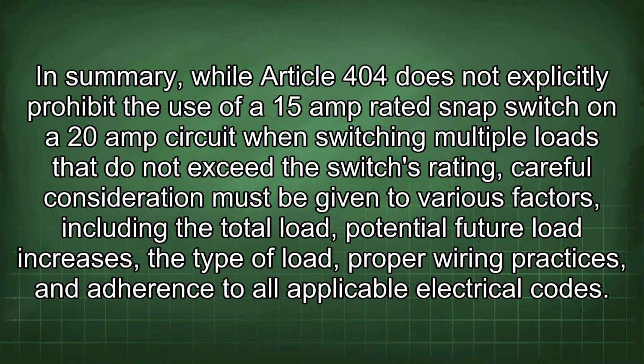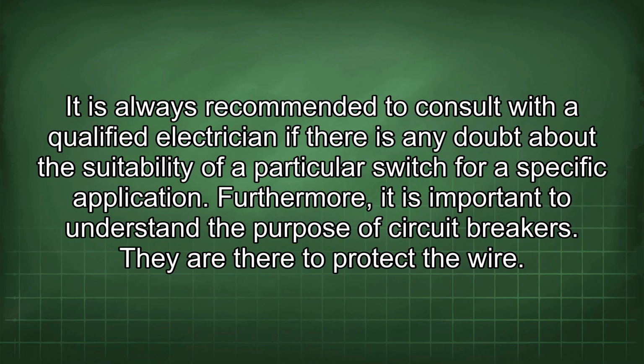In summary, while Article 404 does not explicitly prohibit the use of a 15 amp rated snap switch on a 20 amp circuit when switching multiple loads that do not exceed the switch's rating, careful consideration must be given to various factors, including the total load, potential future load increases, the type of load, proper wiring practices, and adherence to all applicable electrical codes. It is always recommended to consult with a qualified electrician if there is any doubt about the suitability of a particular switch for a specific application.